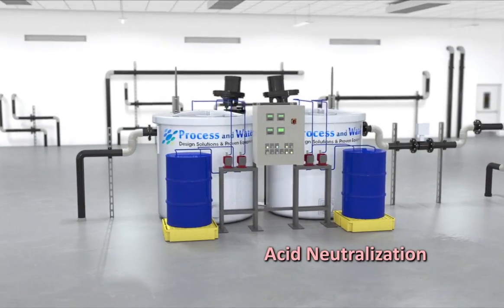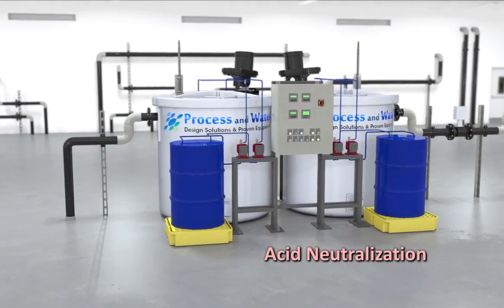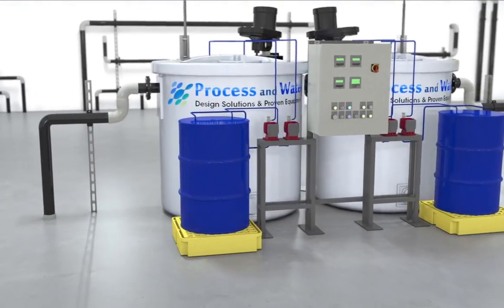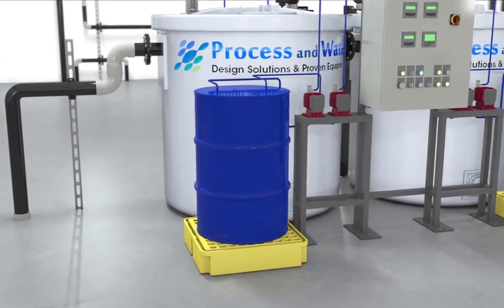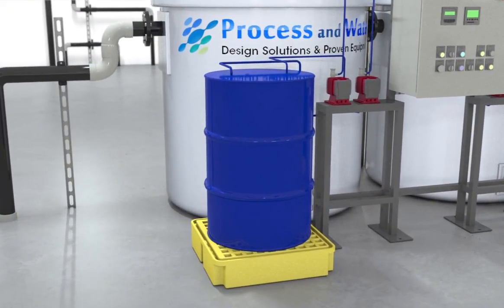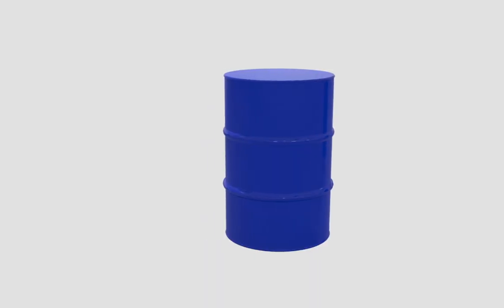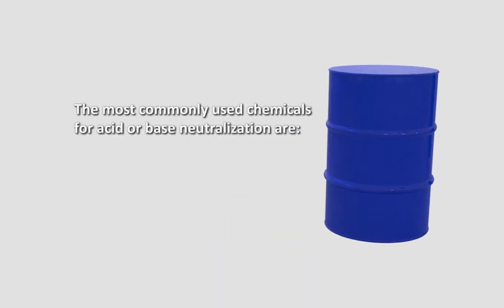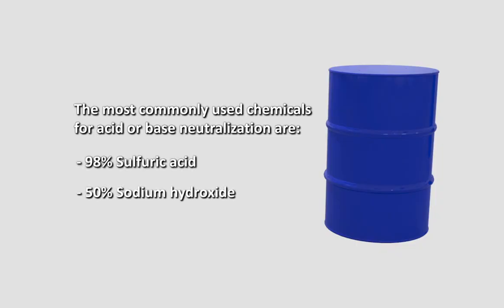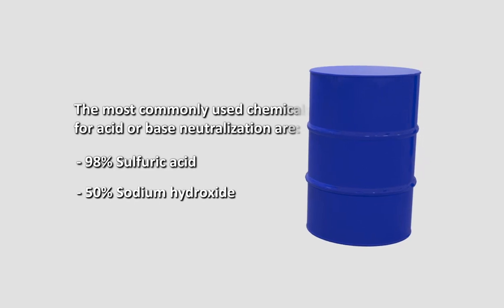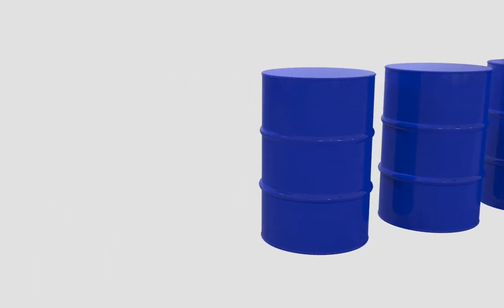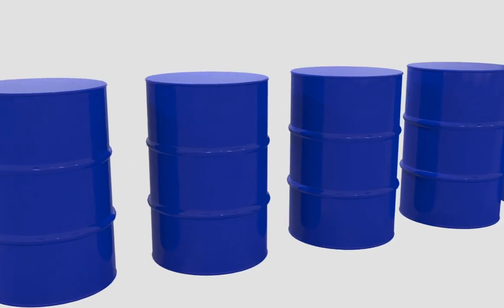In the case of an acid neutralization, caustic, NaOH, is added to the effluent stream to neutralize the pH of the solution. The most commonly used chemicals for acid or base neutralization are 98% sulfuric acid and 50% sodium hydroxide. In many cases, these are very good choices. However, there are many considerations when selecting chemicals, and these may not always be the best selection.